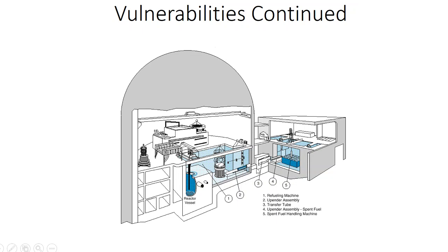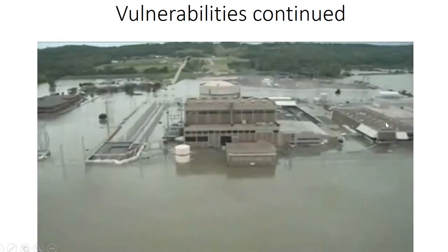So at this point, if something were to happen which would jeopardize our ability to remove the latent heat of criticality from any of these areas and get it transferred either to whatever essential service water cools this down or your shutdown cooling system, your RHR system, you're going to find yourself in an interesting scenario, especially if you can't maintain the fuel covered. Then you're looking at it being more likely to have fuel failure.